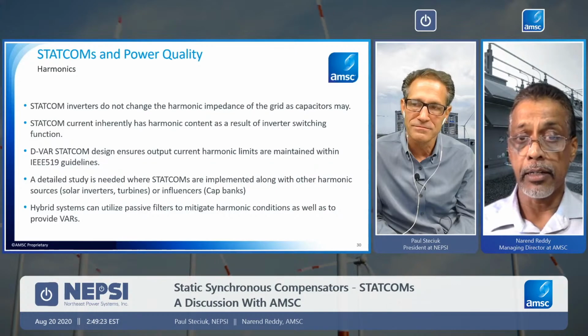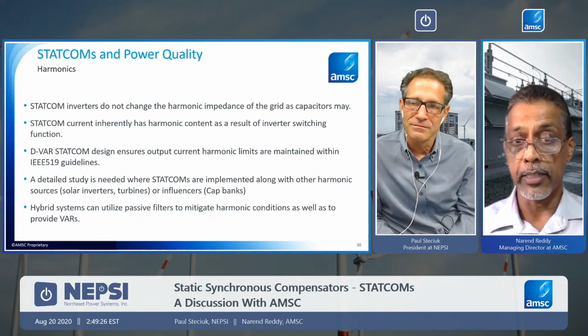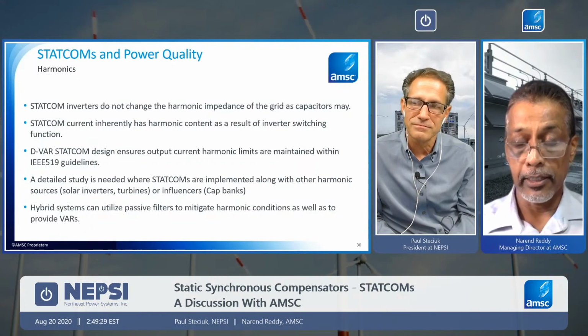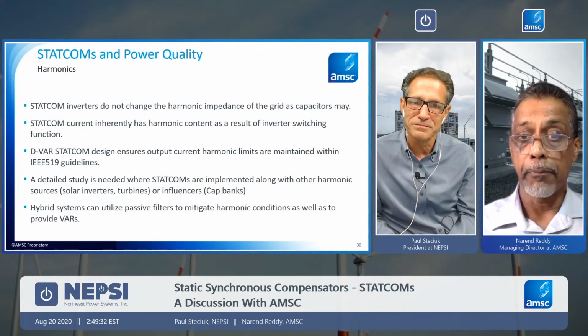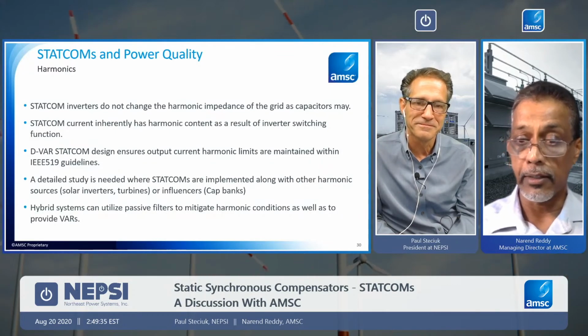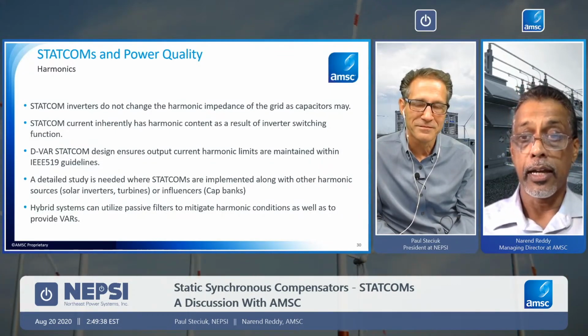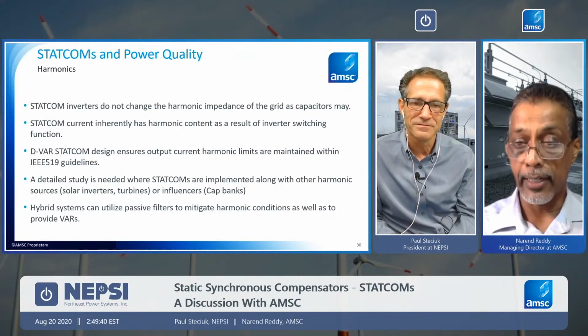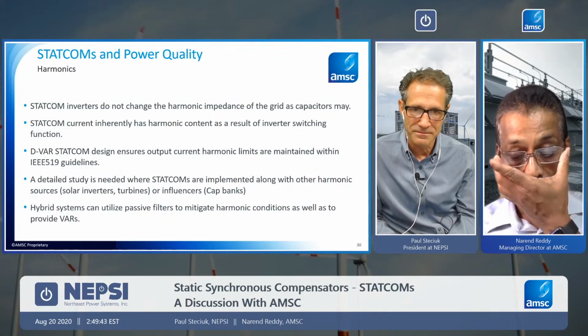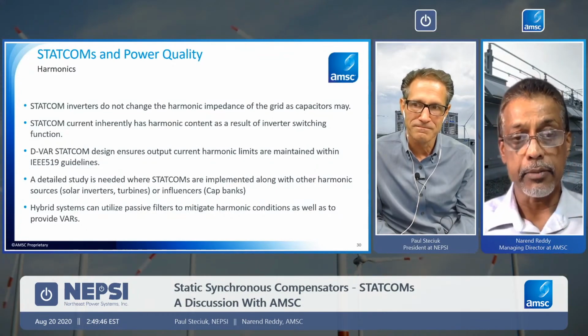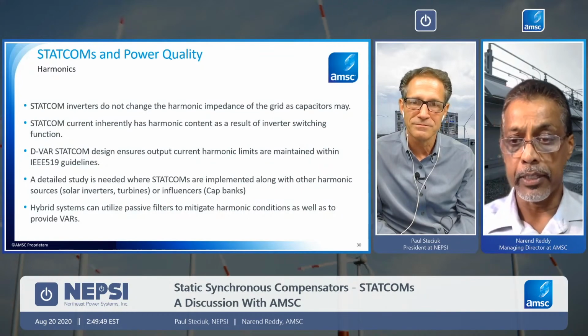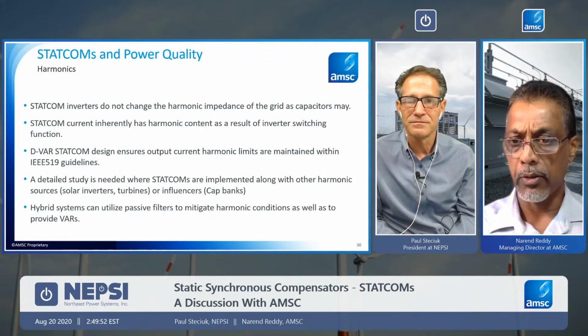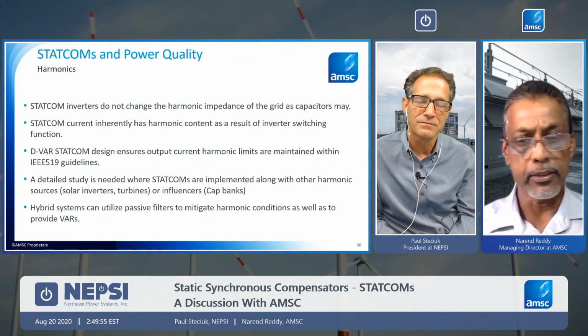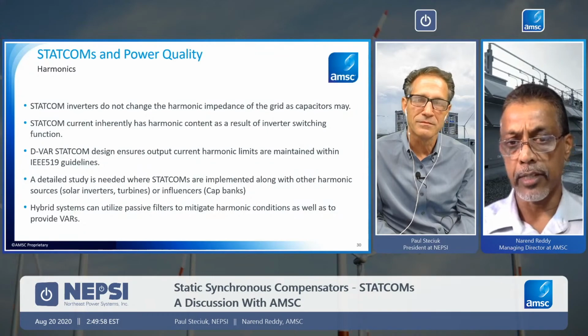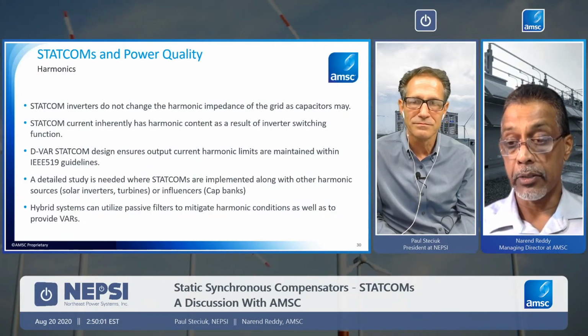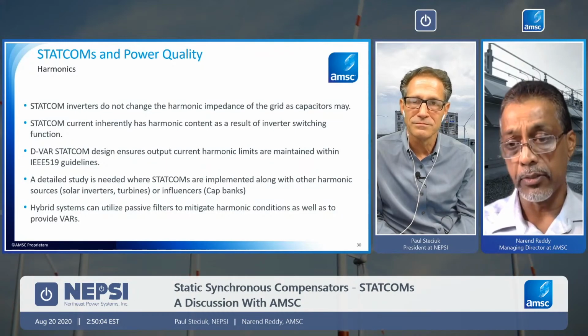The dvar STATCOM, by design, is designed such that the harmonics content of the output current on the other side of the transformer does not violate the IEEE 519 guidelines. And that's something that we design right out of the gate as a standard. But for every project, we look at how many units are going in, what the background impedance for background harmonics is, and whether there are any capacitor banks or other devices that are going to potentially change the harmonic impedance of the grid.